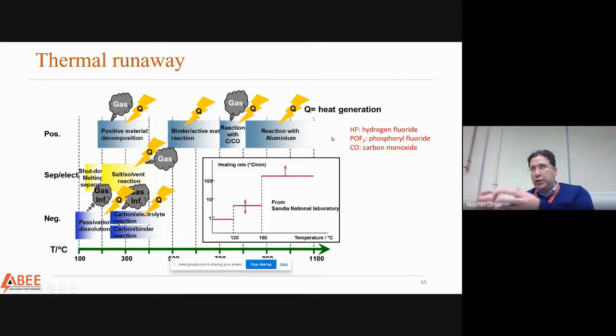When the temperature is around 1,000 to 1,100 degrees, that's where you get an explosion, because the amount of heat at that moment is so huge that you cannot control it anymore. The problem is that a lot of gases are associated with the explosion, and these are typically toxic gases like hydrogen fluoride, phosphoryl fluoride, and carbon monoxide, depending on the battery chemistry, and these are toxic and affect our health.